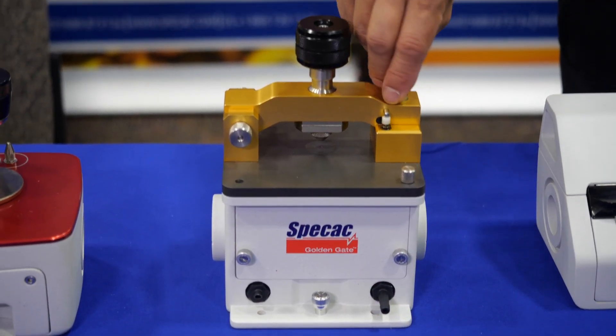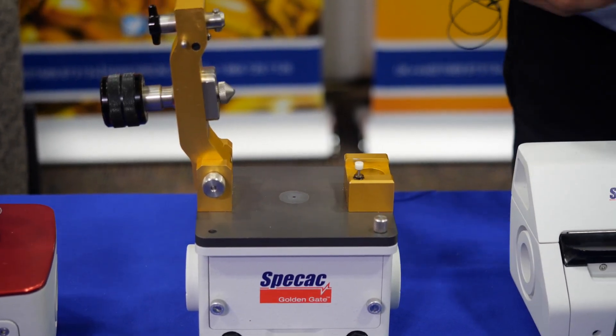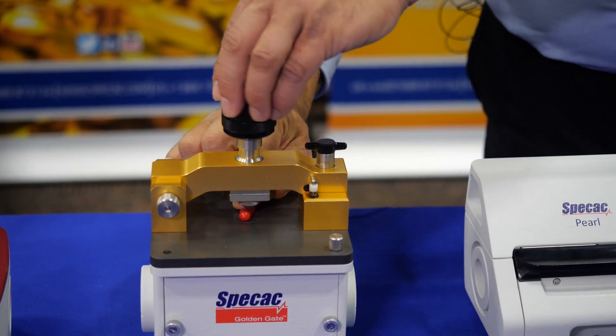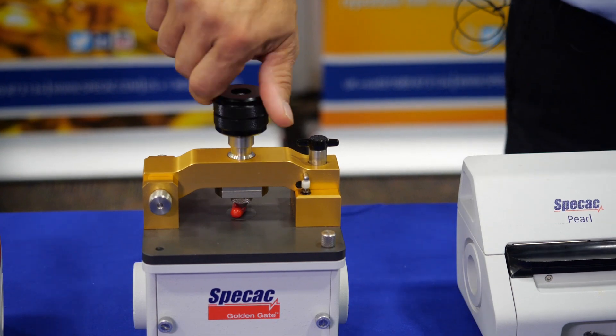Going through them — the ATR — we have several different ATRs. The first one is the Golden Gate, which I would say is the crown glory of the Specac accessories. It is the one that we've had around for close to 30 years. It is a monolithic diamond ATR. Golden Gate has several different top plates, so it's not just an ATR. It has a heated top plate that will go to 200 degrees C. You can do polymer melts with that and look at crystallinity differences and kinetic reactions.